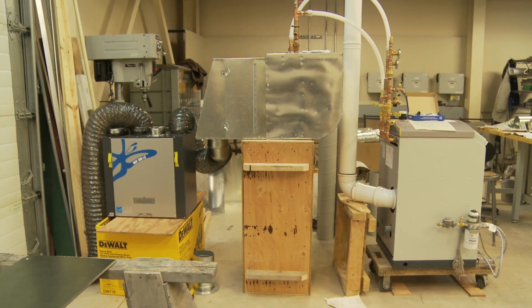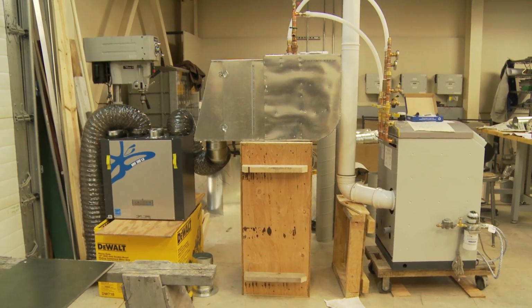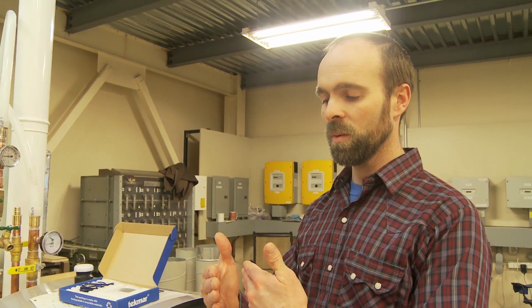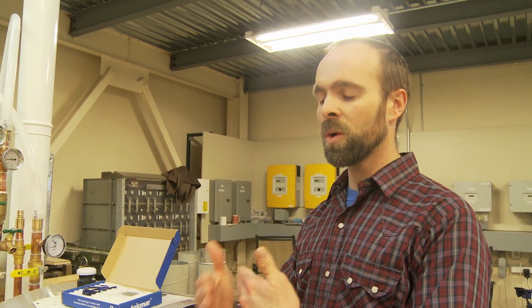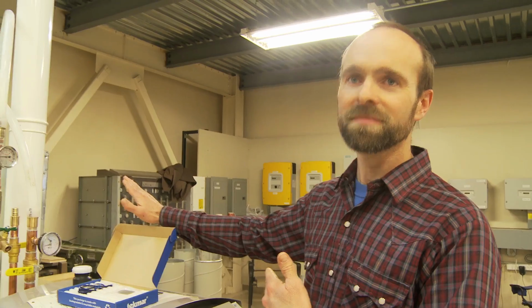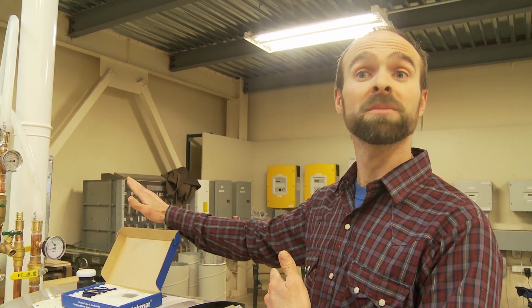Here we have a situation in the village where we want to integrate our ventilation. We want to make sure these people are getting fresh air, and we'll also make sure that they stay warm. We want to combine them because we don't want people turning the heat on and turning off the HRVs. This setup makes that impossible, because if your HRV is on, you're going to get airflow across this heat exchanger and get a warm house. If the HRV is off, you're not going to get any heat in that house in an effective manner.